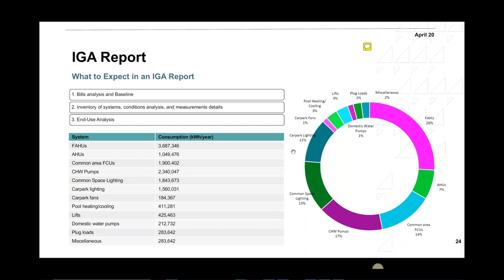Next thing, maybe, chilled water pumps also have higher consumption. So I would look into maybe the outdoor air handling units first, then the chilled water pumps, then the lighting, then maybe the common area FCUs. That constitutes maybe more than 80% of the consumption. Looking at, let's say, domestic water pumps, not much. They don't consume a lot of energy. I don't need to waste a lot of time there.